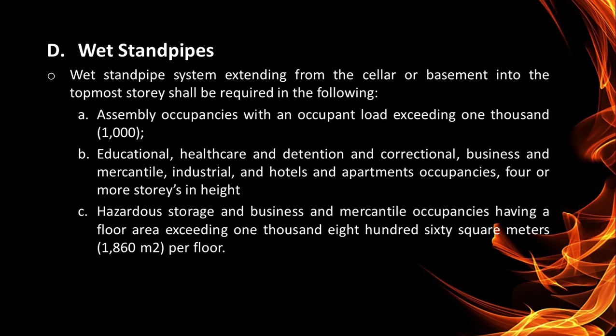Next is wet standpipes. A wet standpipe system extending from the cellar or basement into the topmost story shall be required in the following. First is the assembly occupancies with an occupant load exceeding 1,000. Second is educational, healthcare, and detention and correctional, business and mercantile, industrial, and hotels and apartments occupancies, 4 or more stories in height. Next is hazardous storage and business and mercantile occupancies having a floor area exceeding 1,860 square meters per floor.